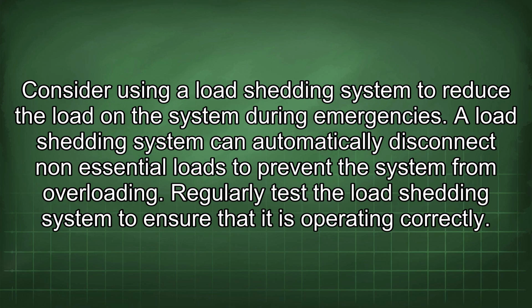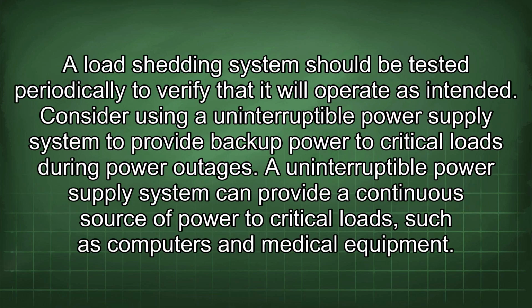Consider using a load shedding system to reduce the load on the system during emergencies. A load shedding system can automatically disconnect non-essential loads to prevent the system from overloading. Regularly test the load shedding system to ensure that it is operating correctly. A load shedding system should be tested periodically to verify that it will operate as intended.